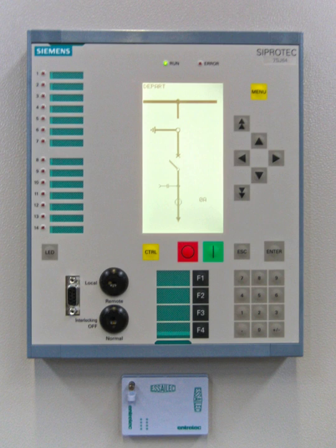This means that when a fault appears on the line, the impedance setting in the relay is compared to the apparent impedance of the line from the relay terminals to the fault. If the apparent impedance is determined to be below the relay setting, it is determined that the fault is within the zone of protection. When the transmission line length is too short, less than 10 miles, distance protection becomes more difficult to coordinate. In these instances, the best choice of protection is current differential protection.